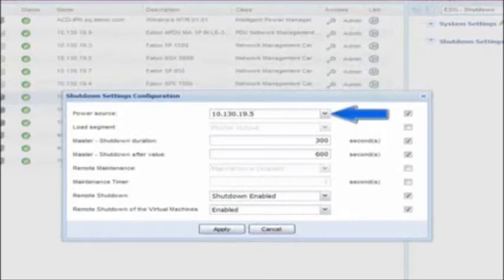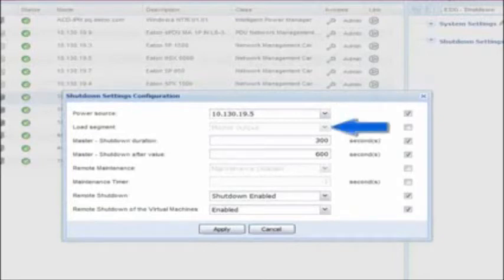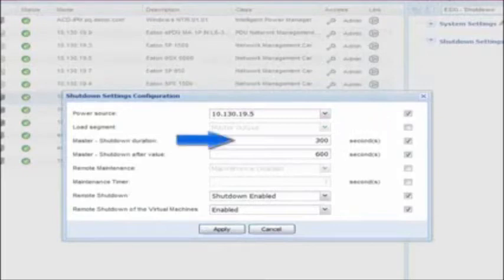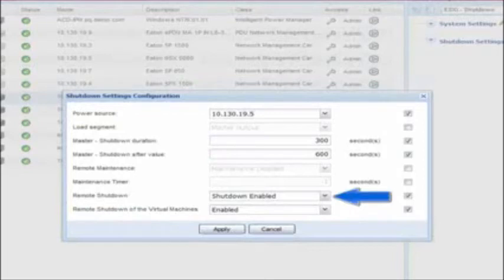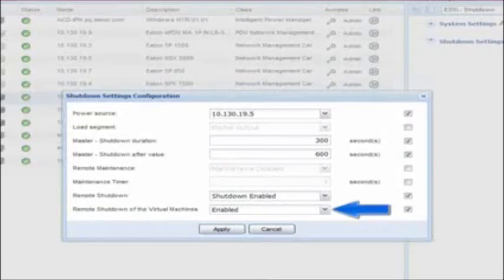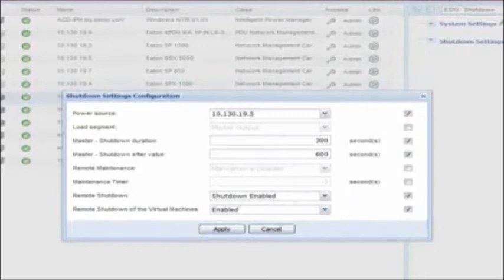Power Source: select the IP address of the UPS which powers your host. Load Segment: designate the output receptacle which the host node is connected to on the UPS — typically this will be the master segment. Master Shutdown Duration: enter an amount of time in seconds which will dictate the length of time the host will have to complete its entire shutdown. The virtual machines will shut down first and then the host. Once the designated time expires, the UPS load segment will de-energize. Master Shutdown After Value: enter an amount of time in seconds which will dictate the length of time IPM will have before it triggers the shutdown of the host. Remote Shutdown: enable this option in order to grant IPM permission to trigger the host to shut down. Remote Shutdown of the Virtual Machines: this option is only used in a high-availability cluster; when enabled, IPM will shut down the guest VMs before shutting down the host. Click Apply to activate the settings.